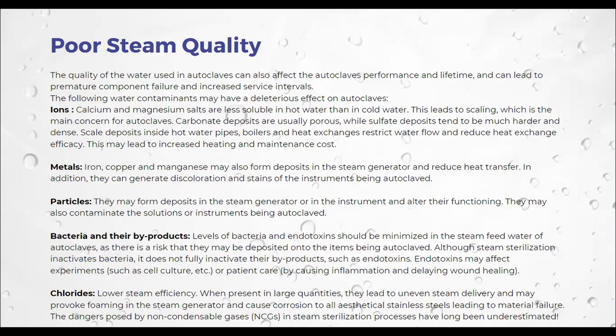And then we must look at bacteria and their products. The level of bacteria and endotoxins should be minimized in the feed water of the autoclave, as there's a risk that they may deposit onto the item being autoclaved. Although steam sterilization inactivates bacteria, it does not fully inactivate their byproducts, such as endotoxins, and may affect experiments such as cell culture or patient care by causing inflammation and delaying wound healing.